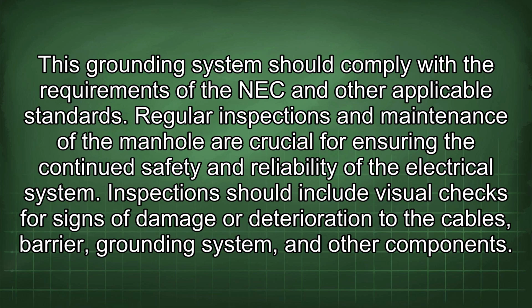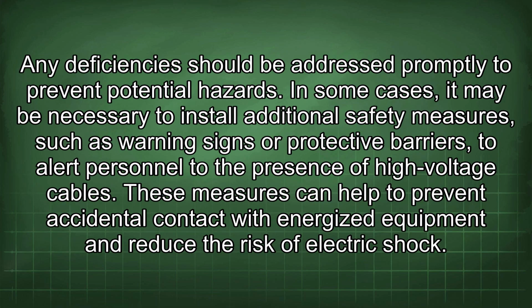Inspections should include visual checks for signs of damage or deterioration to the cable's barrier, grounding system, and other components. Any deficiencies should be addressed promptly to prevent potential hazards. In some cases, it may be necessary to install additional safety measures, such as warning signs or protective barriers to alert personnel to the presence of high-voltage cables. These measures can help to prevent accidental contact with energized equipment and reduce the risk of electric shock.